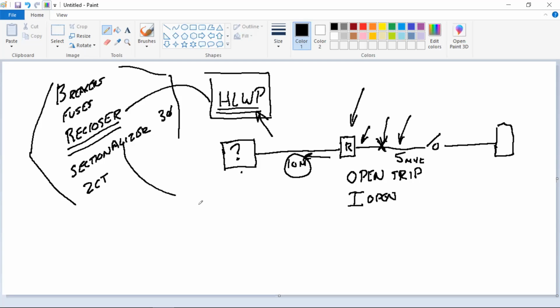How about a sectionalizer? Three-phase. What does a three-phase sectionalizer do? Does anybody remember? Opens all three phases at one time. How many occurrences? Once. There you go. Sectionalizers don't reclose to start with. You've got one instance, especially on a three-phase one. One instance is you're going to see a fault, and it's going to open. So do I need to get a hotline work permit? We'll change this to an S on this circuit. Do I need to get a hotline work permit on the breaker if I've got a sectionalizer working in here? No. Good answer.